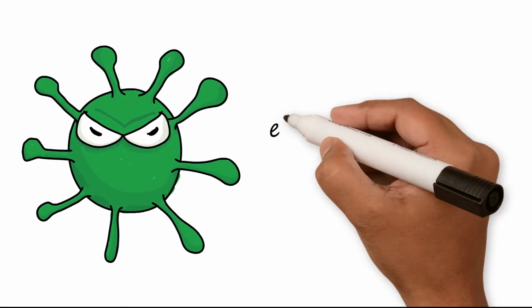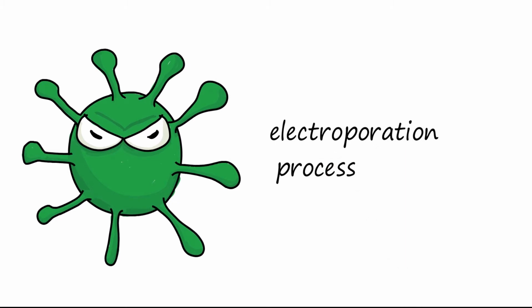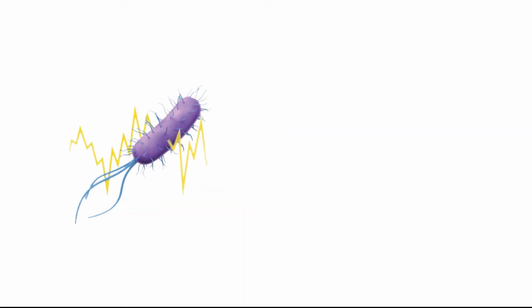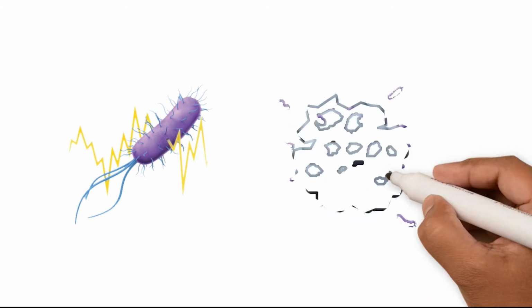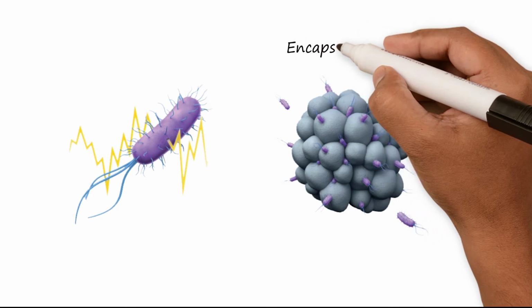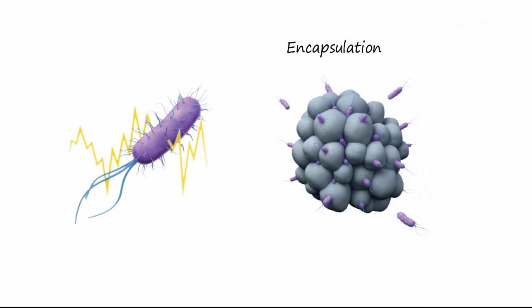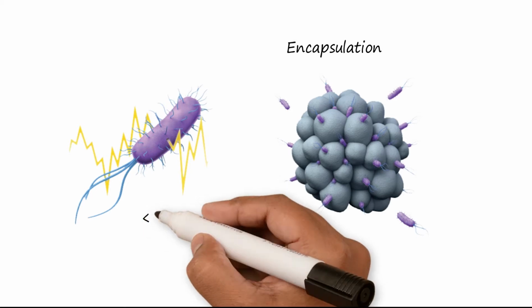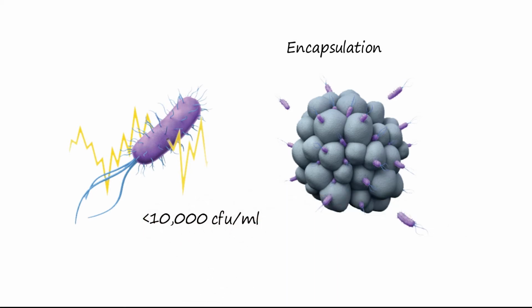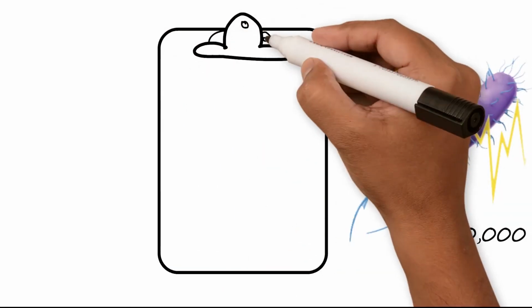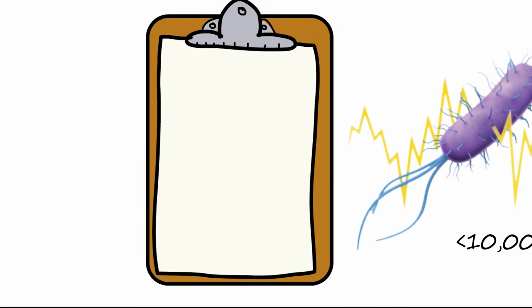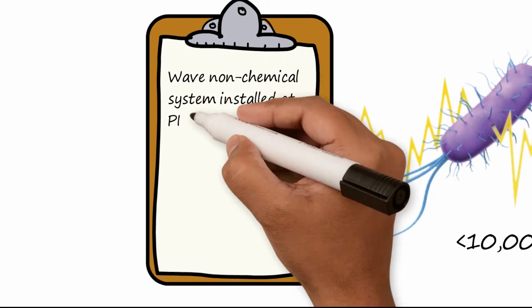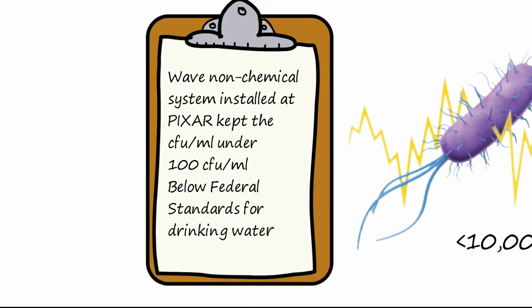For bacteria control, the Wave uses an electroporation process which has been used in cold pasteurization for decades. The high-frequency pulses from our electrodynamic field damage the cell walls of bacteria, weakening them, preventing reproduction, and ultimately inactivating them. Through encapsulation, bacteria is also drawn into the suspended particle mineral formations, becoming eventually stuck and encapsulated with the harmless powder. The Wave's bacteria levels are way below the Cooling Tower Institute's guidelines of 10,000 CFU per ml, and a recent ASHRAE study of a Wave installation at Pixar Studios revealed bacteria levels under 100 CFU per ml. This is far below the federal standards for drinking water.